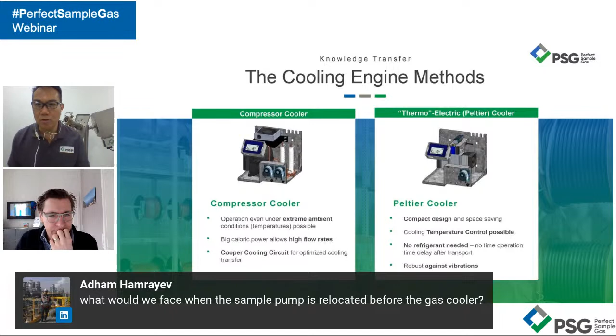Why? Because the main purpose of the gas cooler is to handle high acid dew point. The sample heated line has a very high temperature, and we need this high-temperature sample, above the acid dew point, to go into the gas cooler to remove the water. Just imagine putting a gas sample pump in between - that means your pump would have to handle the high sample temperature. The answer is no. So don't do that. Put the pump behind the gas cooler.